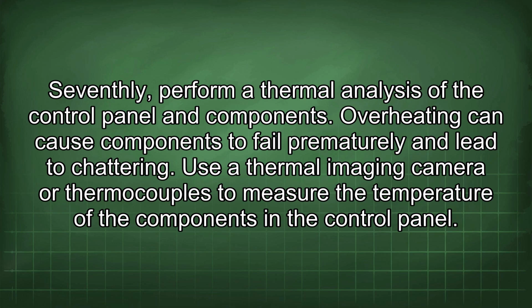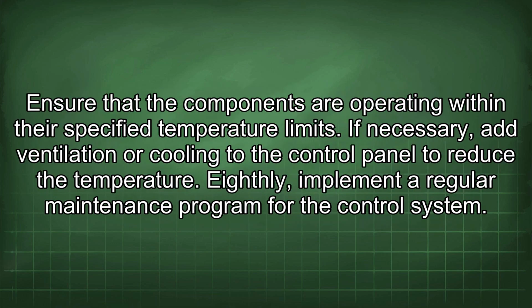Use a thermal imaging camera or thermocouples to measure the temperature of the components in the control panel. Ensure that the components are operating within their specified temperature limits. If necessary, add ventilation or cooling to the control panel to reduce the temperature.